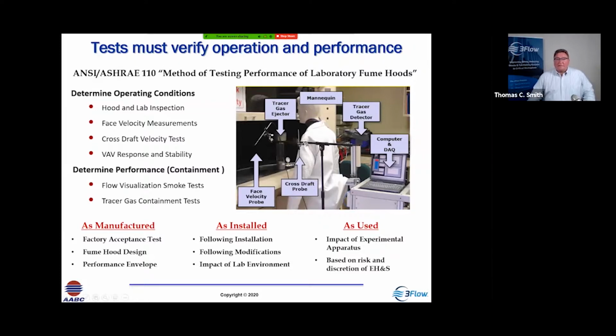From here, the flow visualization, that's not a big deal. That's a fog generator or smoke tubes, smoke sticks. Again, that's a low-cost item. But it's the tracer gas containment test where you start getting into the big expense and the complications. The meter itself, $30,000 to $40,000. The whole equipment apparatus, you've got to have a mannequin, the generator, the tanks, the regulators. You're into it about $50,000, $60,000 worth of equipment. And then there's the ongoing maintenance, calibration, procedures, training, and so forth to do it.